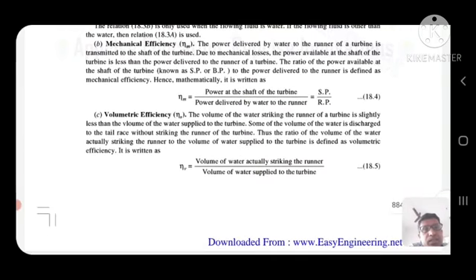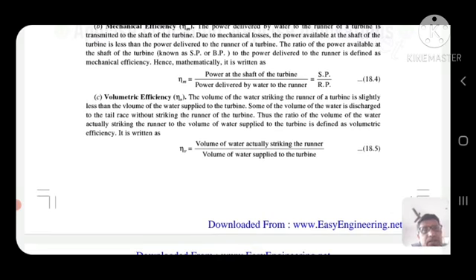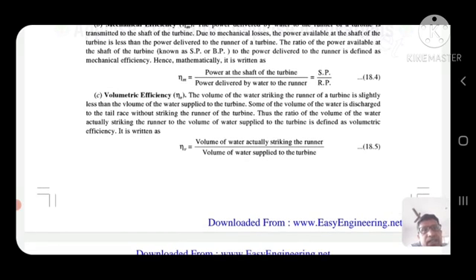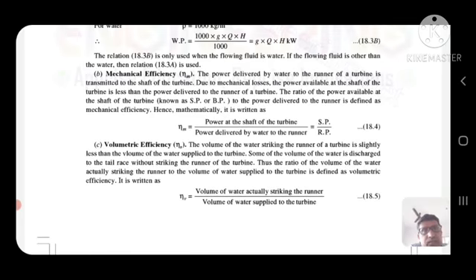Mechanical efficiency: the power delivered by water to the runner of a turbine is transmitted to the shaft of the turbine. Due to mechanical losses, the power available at the shaft of the turbine is less than the power delivered to the runner. The ratio of power available at the shaft of a turbine to the power delivered to the runner is defined as mechanical efficiency. Mathematically, mechanical efficiency = power at shaft of turbine / power delivered by water to the runner.